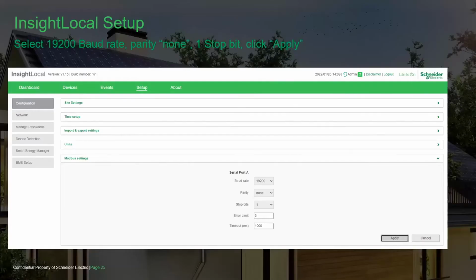Once logged into your Insight local web page, click the setup tab and you'll see the Modbus settings section. Expand that, select the baud rate of 19,200, parity none, and a stop bit of 1, then apply that.